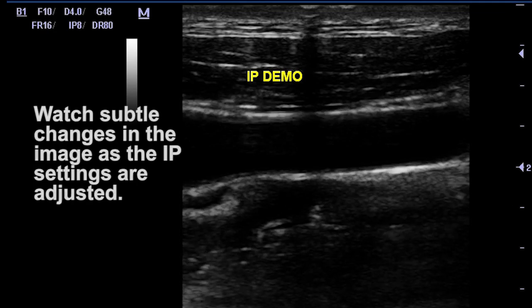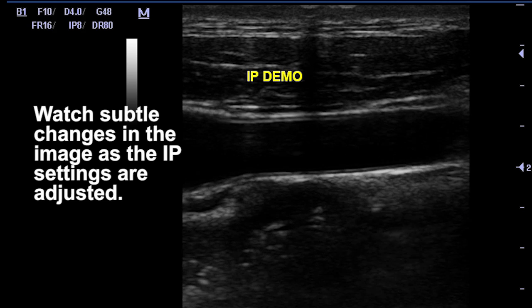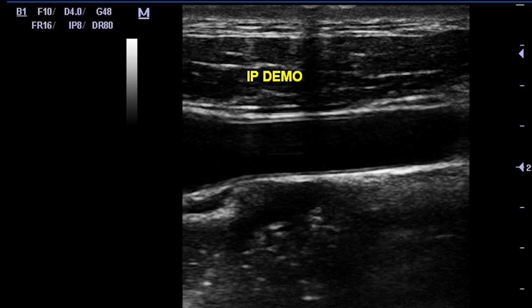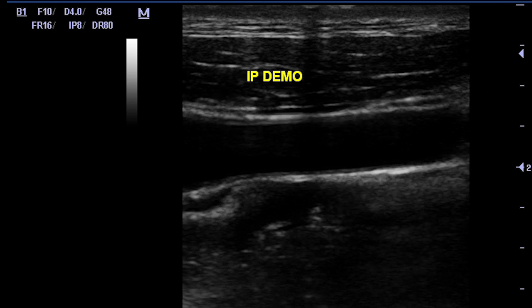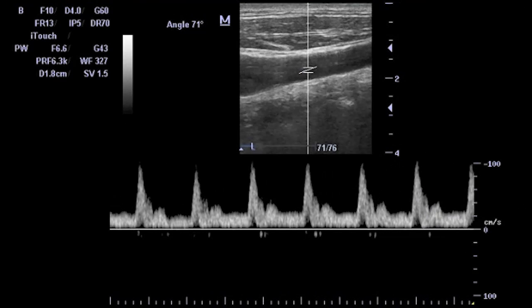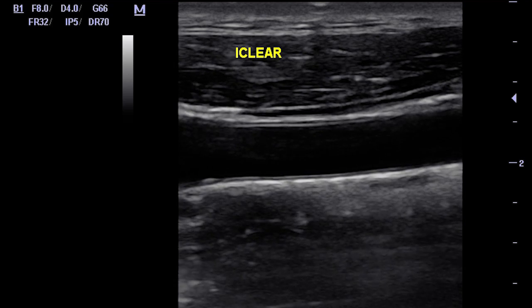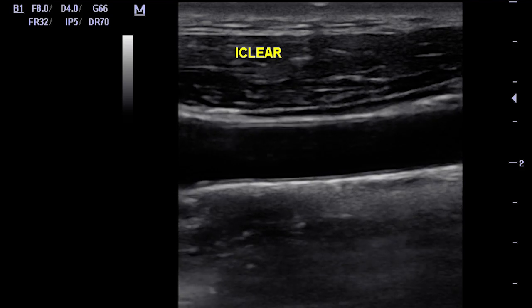The Mindray also has something you won't see on others — it's called IP Processing. It's image processing that allows you to adjust a number of parameters including dynamic range, persistence, and line density, all at the single touch of a button. Just click it up and down to find the setting you like without having to change a bunch of knobs simultaneously. It allows you to optimize the image for what you like to see, whether you prefer Acuson, Terason, or Philips images — it will smooth or give you a high contrast ratio while still delivering excellent image quality. That's why we like the M5 so much as a great new portable ultrasound choice.